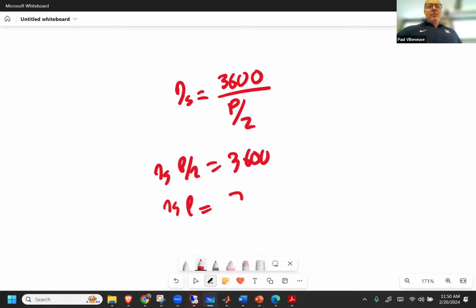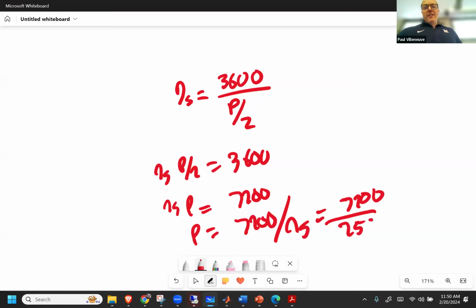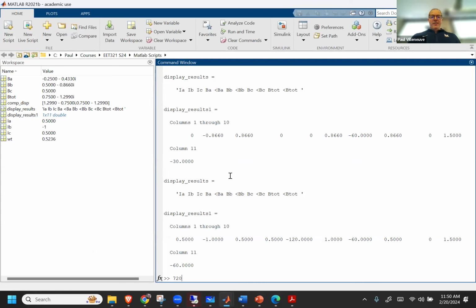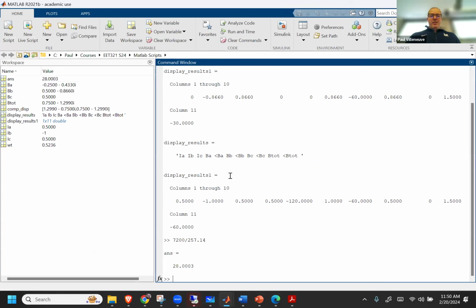NS times P equals 7,200. P equals 7,200 divided by the synchronous speed, which is 7,200 divided by 257.14. That's 14, let's try it. 7,200 divided by 257.14... no, times 2. 7,200 is times 2, but then you divide by 2. So there's 28 poles, or 14 pole pairs. Yes, 14 pole pairs.